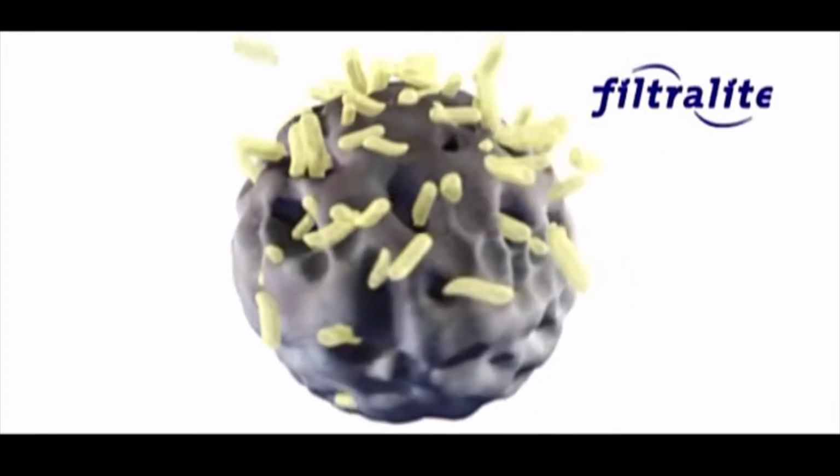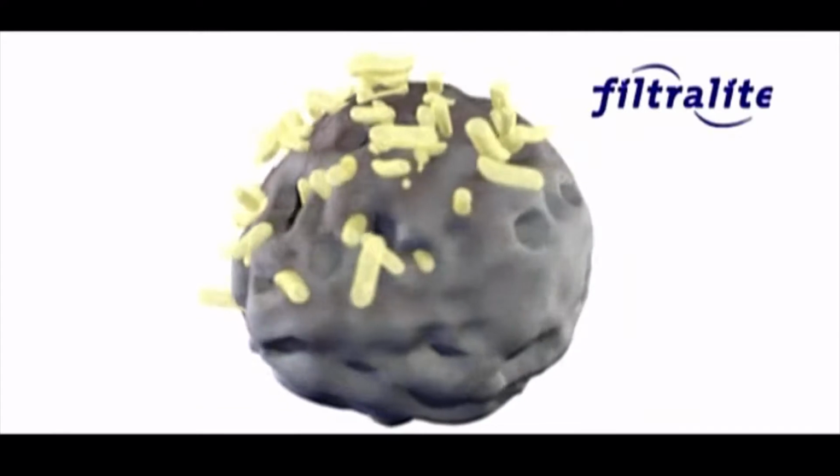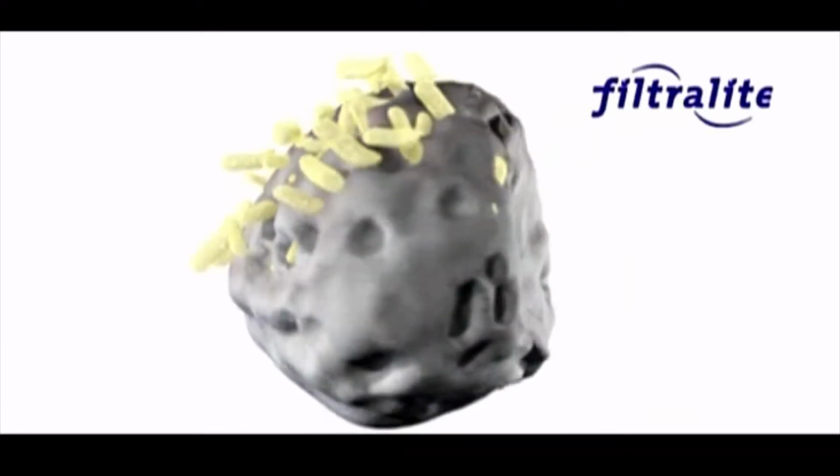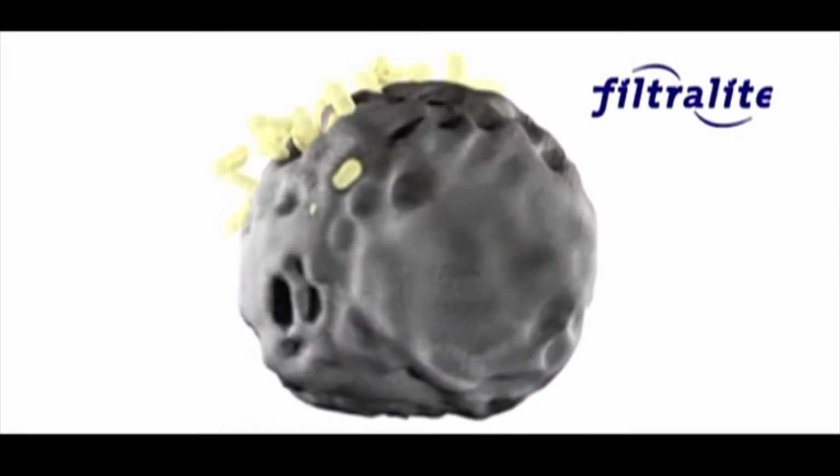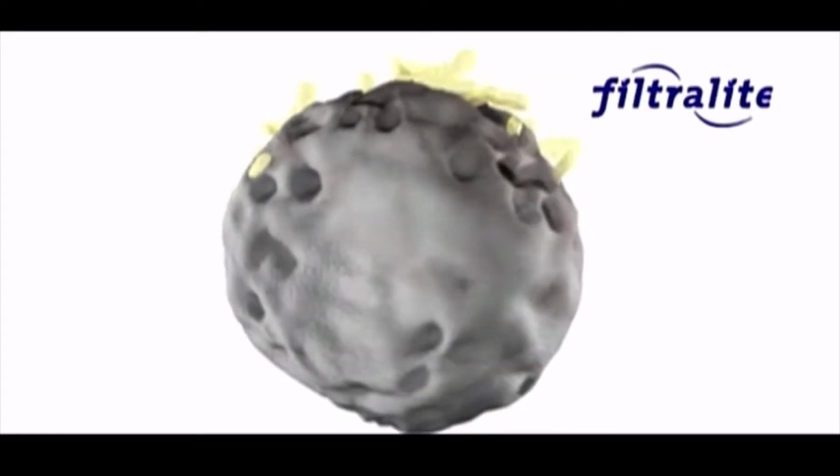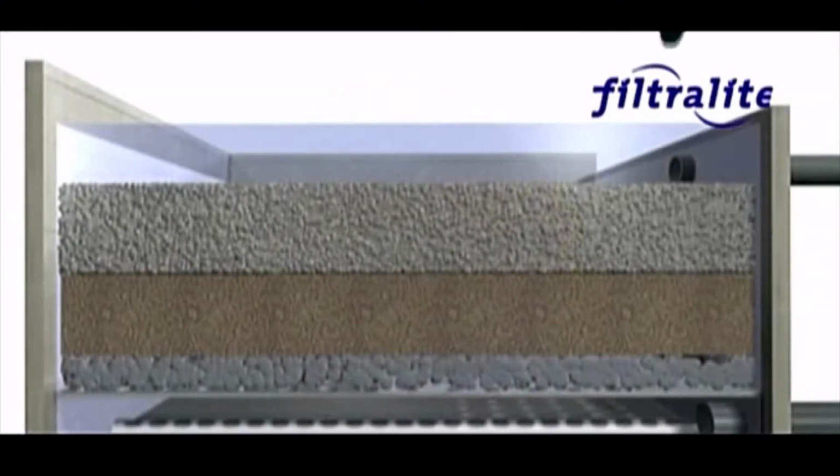The retained floc will after a while saturate the filter, and the turbidity out of the filter will be too high. The filter then has to be stopped for backwashing. This is carried out by flushing water and air up through the filter. The most recommendable way of cleaning the filter is with air and water in combination.